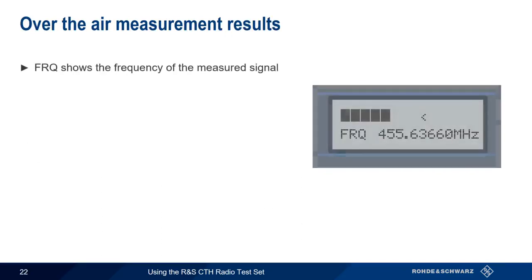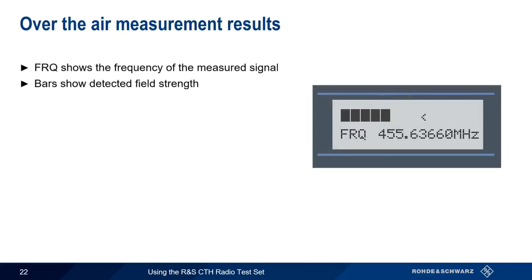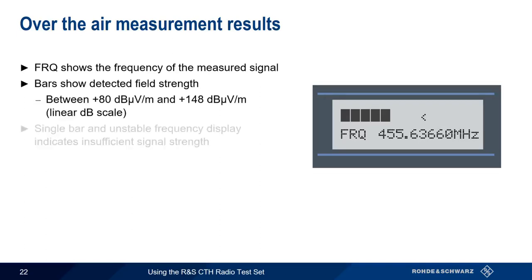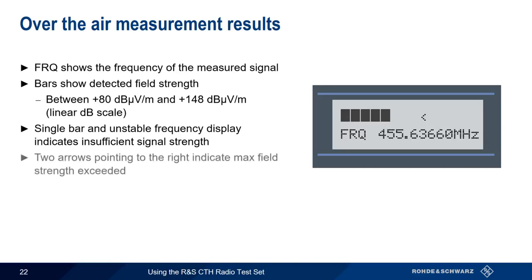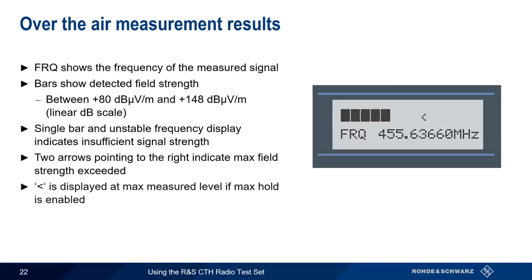The frequency of the measured signal is given in megahertz, and field strength is shown as a series of bars representing values between +80 and +148 dB microvolts per meter, using a linear dB scale. A single bar, or an unstable or changing frequency display, means there is insufficient signal strength for a measurement — in this case, move the CTH closer to the transmitting radio or antenna. Two right-pointing arrows indicate that max field strength has been exceeded. If Max Hold was enabled under Settings, a less-than sign indicates the maximum measured signal strength during the Max Hold period.